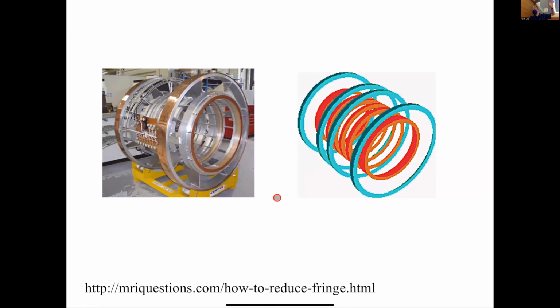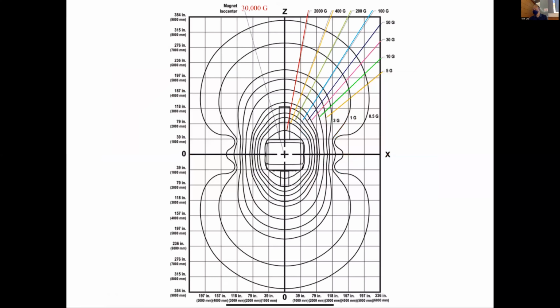Typically most designs now have a main set of wires inside, shown here in red, and then there'll be counter windings that create a magnetic field in the opposite direction. So you cancel out the field outside without really perturbing the field inside. That's what's called the self-shielded magnet. Every magnet you get will typically come with a pattern of the field strengths. This is a 3 Tesla magnet. In the center of the magnet, you're at 3 Tesla or 30,000 Gauss. The point that we like to be at is half a Gauss.